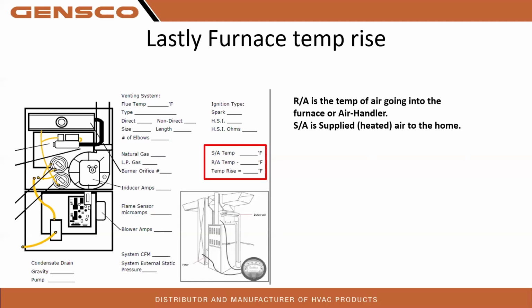So we need to either look at ductwork or add maybe more blower, or here's the direction we need to go down, right? So there's instances where high statics in a home happen, or howling returns or something like that. So we can take this data and go, okay, we're staying within the furnace running parameters, minimum and maximum, but we have these other issues, a howling return or homeowner noise at a register boot. So, okay, knowing that we're on the high end of that temperature rise, we can't slow down that blower because then we'll have an overheat situation, right? So all this data collected is going to give us a lot of information.